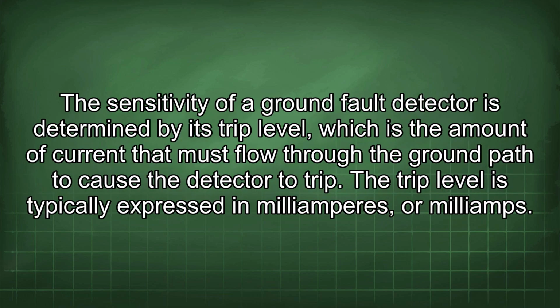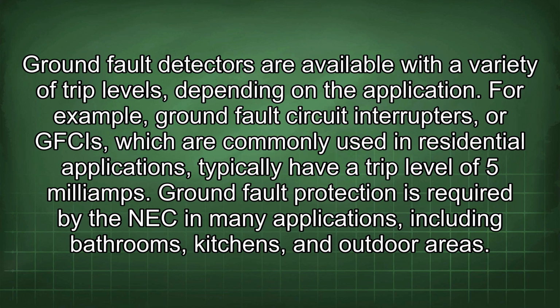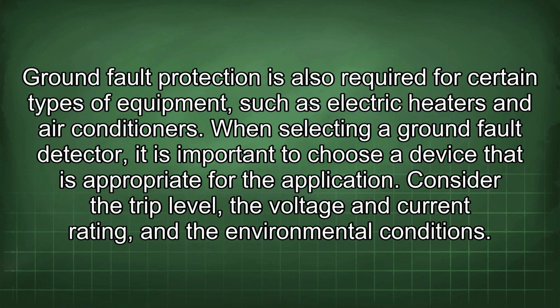The sensitivity of a ground fault detector is determined by its trip level, which is the amount of current that must flow through the ground path to cause the detector to trip. The trip level is typically expressed in milliamperes or milliamps. Ground fault detectors are available with a variety of trip levels depending on the application. For example, ground fault circuit interrupters, or GFCIs, which are commonly used in residential applications, typically have a trip level of 5 milliamps. Ground fault protection is required by the NEC in many applications, including bathrooms, kitchens, and outdoor areas. Ground fault protection is also required for certain types of equipment, such as electric heaters and air conditioners.